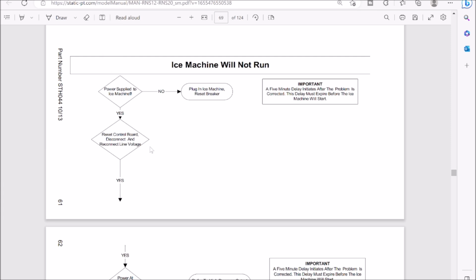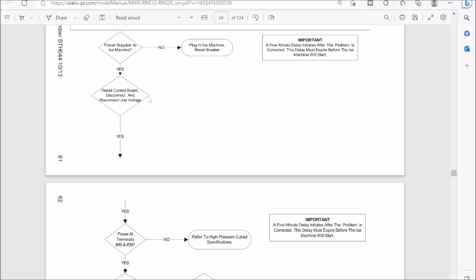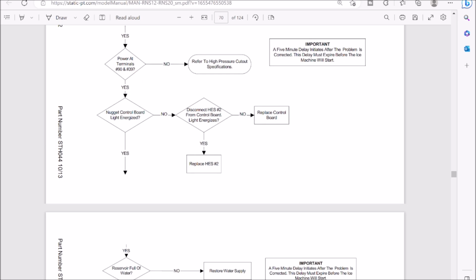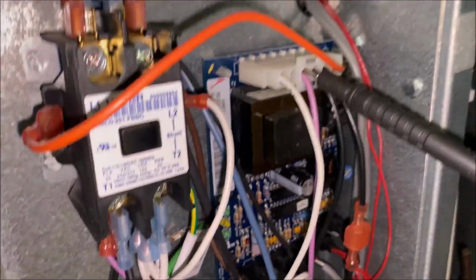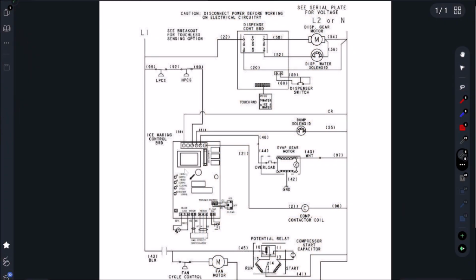Okay. So here it's telling me to reset the control board, disconnect and reconnect line voltage. I do not want to do that. Okay. Because I'm going to have a 15-minute delay. So the next step now is power at terminals 90 and 39. All right, so we're checking for power here. At terminal 90, we have 0 volts. All right, so we just tested on terminal 90, which is right here, wire 90.